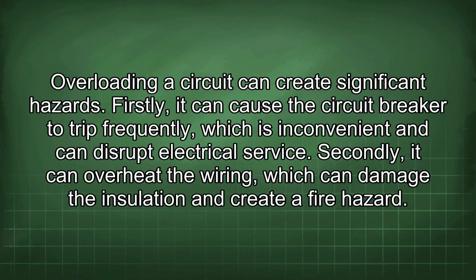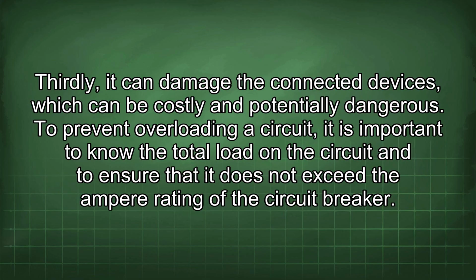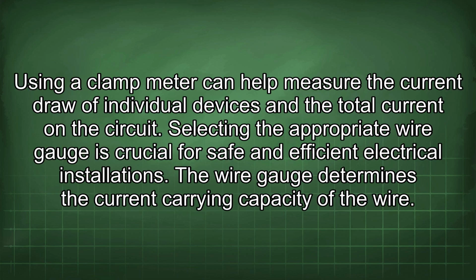Overloading a circuit can create significant hazards. Firstly, it can cause the circuit breaker to trip frequently, which is inconvenient and can disrupt electrical service. Secondly, it can overheat the wiring, which can damage the insulation and create a fire hazard. Thirdly, it can damage the connected devices, which can be costly and potentially dangerous. To prevent overloading a circuit, it is important to know the total load on the circuit and to ensure that it does not exceed the ampere rating of the circuit breaker. Using a clamp meter can help measure the current draw of individual devices and the total current on the circuit.